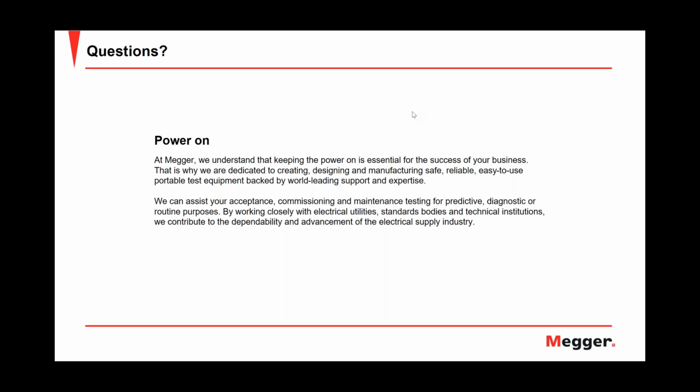So it's nothing prolonged, first of all. It takes like 10 seconds. Because you start at 0, you saw it in the demonstration when he said, what does a fault location situation look like? Let's say I take a SmartThump 16, you saw this needle going up, and then you saw breakdown at 1.6. So that was like 10 seconds. So it is not really a proof test.